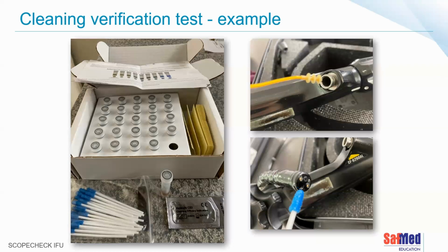There's an example of one such product. It's a vial with liquid in it, generally supplied with some smaller swabs, and separately you'd buy longer testing swabs like these. They come in different diameters, as we have different diameters for biopsy channels and working channels. With the shorter swabs you can test the tip of the scope, the biopsy port, the valve ports, or any other area of the scope on the exterior. Internally, though, we need a long brush-like testing swab or brush, depending on what the product provides.